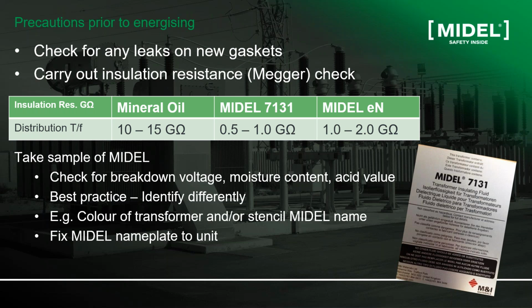Of course, after retrofill, as I mentioned, we take a MIDEL or ester sample. We check the breakdown voltage, the moisture content, and the acid value. These should be within the in-service limits, which I will talk about later. And best practice, when you retrofill a transformer, is to identify it differently so that no one else will come and top up with mineral oil, and so defy the purpose of a K-class. Sometimes you can color the transformer differently or mount a plate identifying the retrofilled liquid and the date of retrofilling.